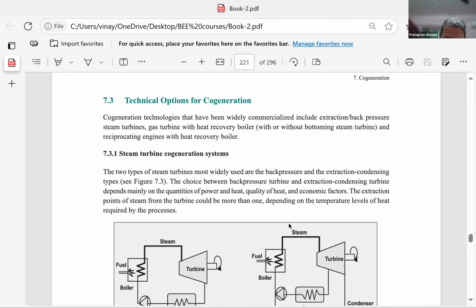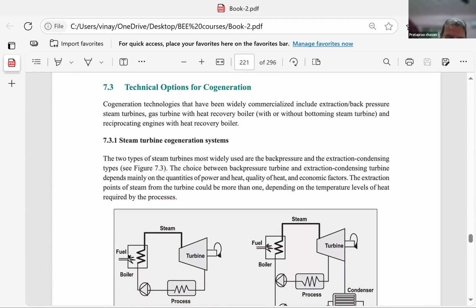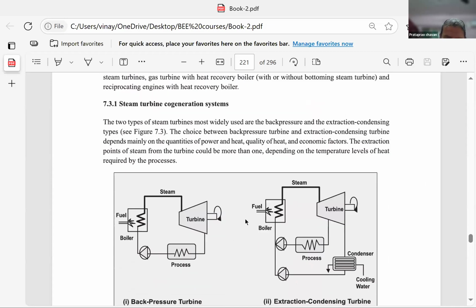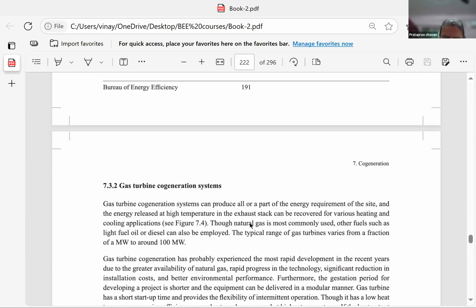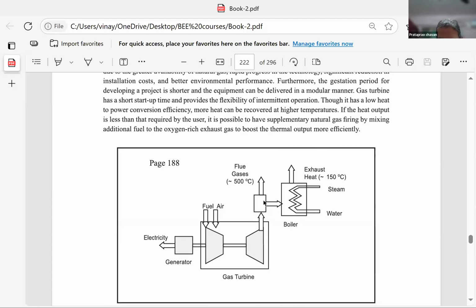The boiler here, right? Here the boiler is getting the heat due to burning of fuel. Combustion takes place here, and in the combustion chamber, heat is transferred to the steam formation. Same activity happens here.